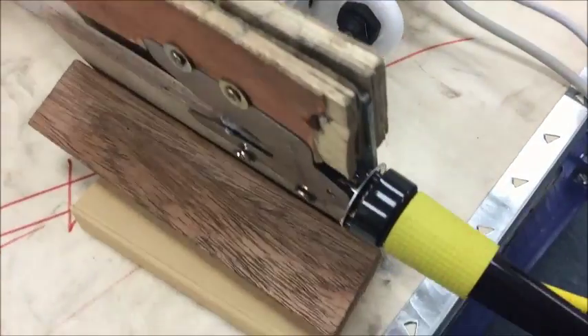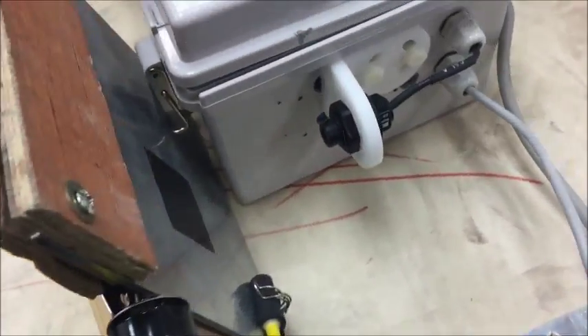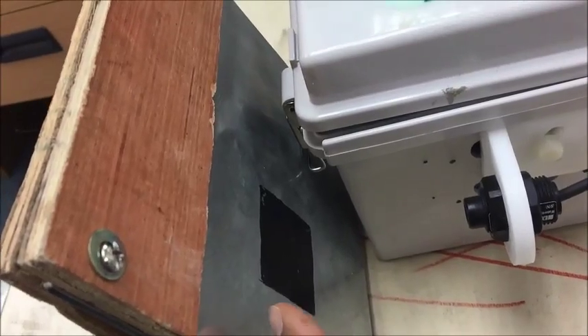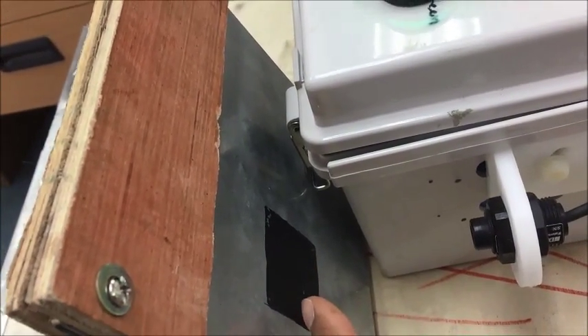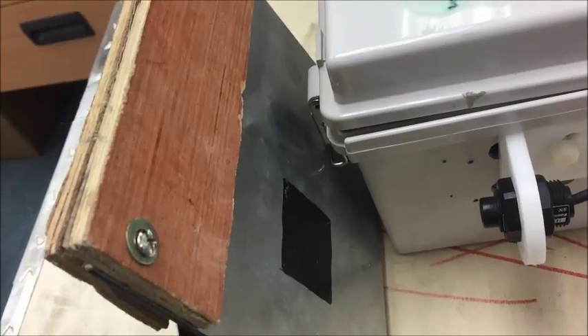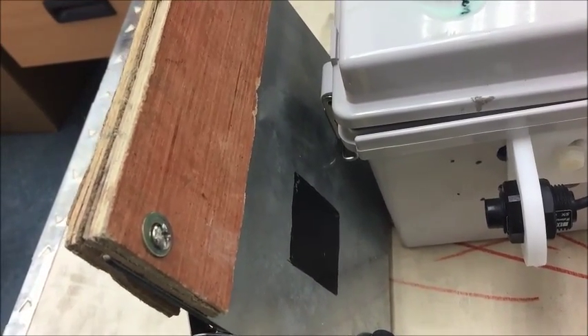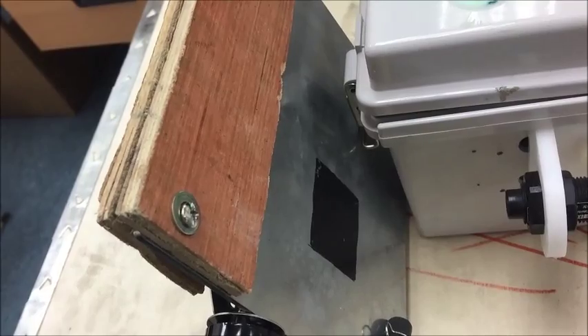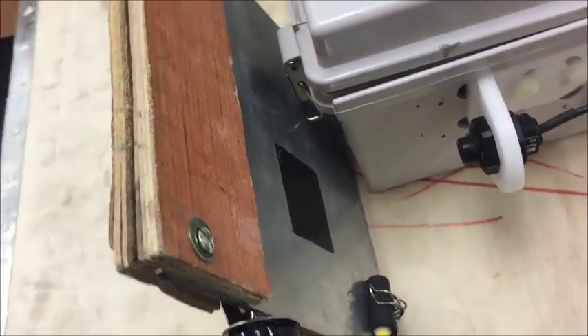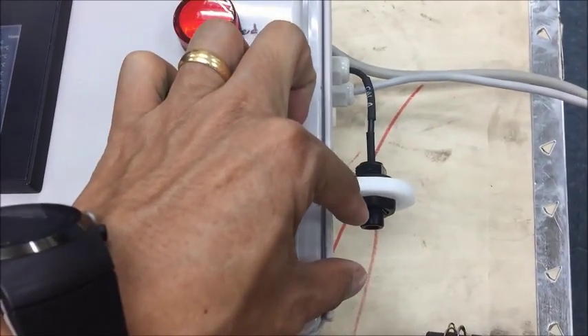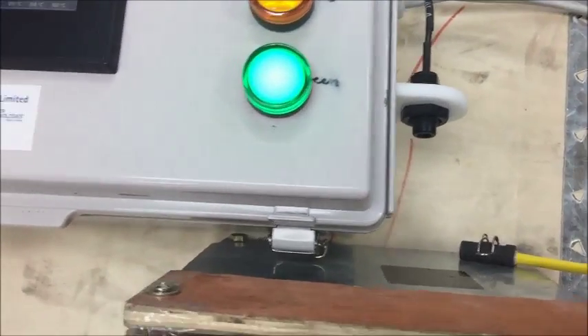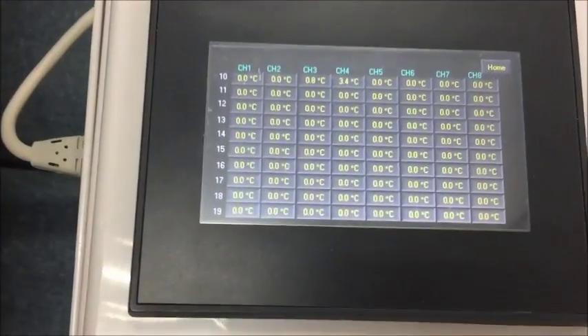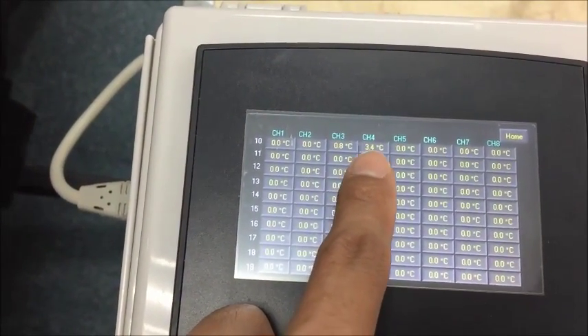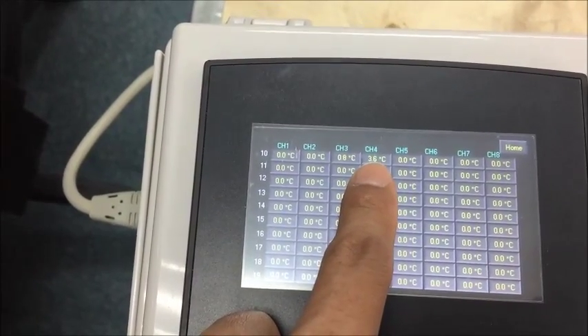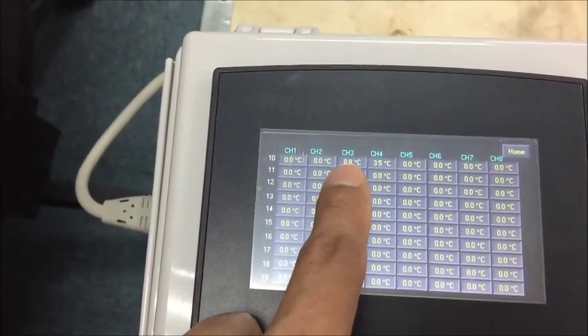and we have a simulation with a hot soldering iron. This is a simulation of a bus bar with a matte black surface, for emissivity itself 0.9. If it's reflective, it's 0.2 emissivity. The distance can be from 1 cm to 30 cm away. Now you can see channel 4 is actually for the IR sensors, and this is for the cable sensor itself.